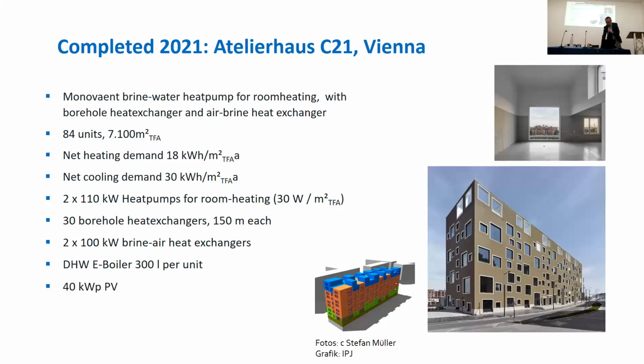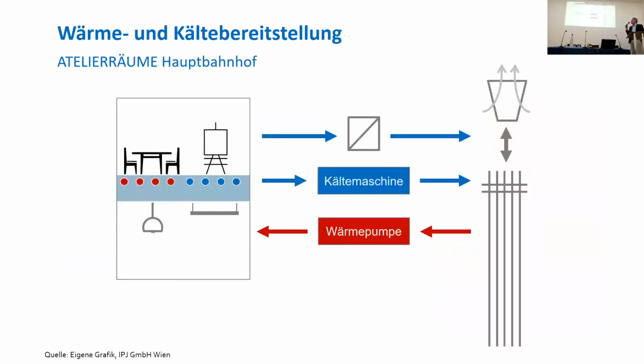And the system is like this: floor heating and cooling, floor because it's an office. And most of the cooling is done, really nowadays everything, with the heat exchanger, recharging the boreholes. And the boreholes are taken as a source over the heat pump. Sorry, it's German, to heat the house. And as an exchange element, we have an air to brine heat exchanger too, that can help us recharge the boreholes if needed during the summer, or that can help to extract heat during the winter if they have too much.